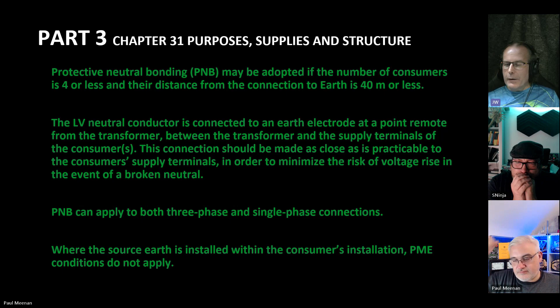The only place I've seen this is in some of the network's actual design documents, and there was one example given where it was a rural installation with a transformer on a pole in the front garden or something, and that was the PNB link there, and then you add your conductors from that to a couple of cottages or something separate to it. So it does exist, but it's certainly not a common thing, and it's not something that you're going to come across that often. Most of it is where you've got a single site and it has its own transformer, and that's where the link is, and it just provides energy to that particular site only. So hence the railway place and various other larger installations.